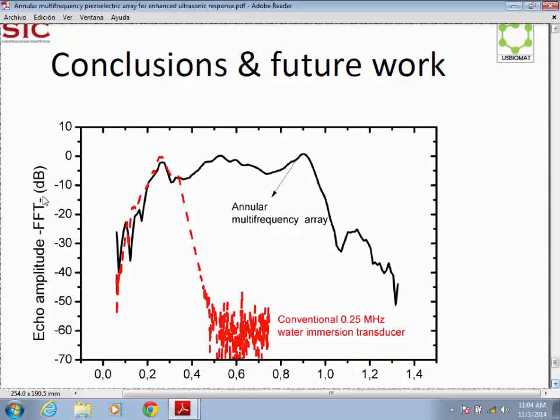Yeah, the crosstalk was very low, because the composite we're using is like columns of fibers that are embedded in an epoxy matrix. So the crosstalk between elements is very low because of this epoxy matrix. So really, the thickness mode is the only one enhanced. So you can just see this mode of operation in the system.